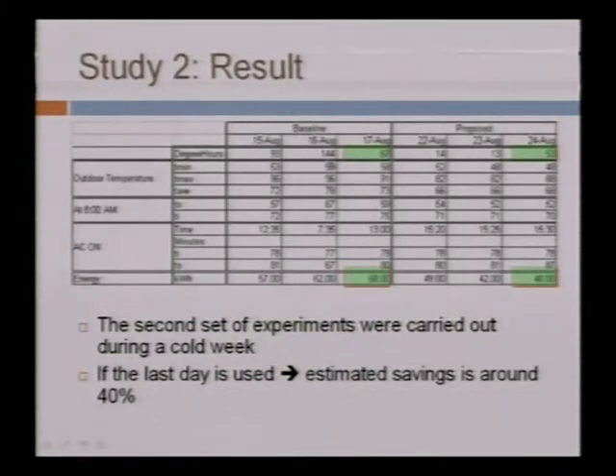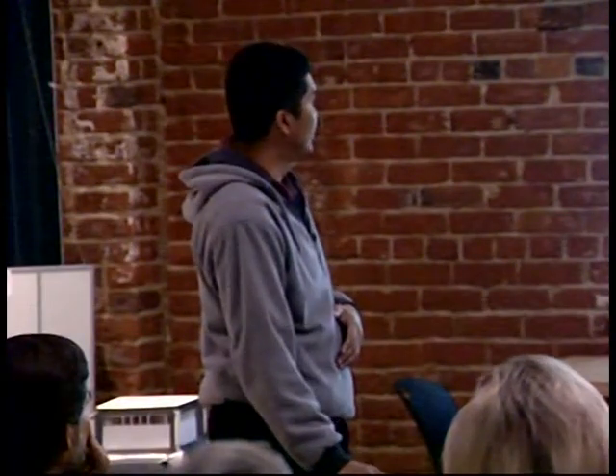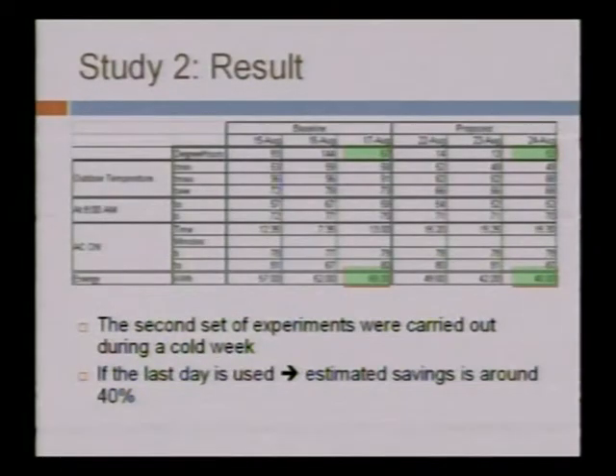But then again, we have the degree hours, which unfortunately, the proposed scenarios were carried out on a very cool week. Very cool week. So, if we want to compare, comparing this and this is not fair, because the cooling load is so much different. So if you compare the similar degree hours, which is on the third day, we can see that there is a 40% savings on the total energy, not only for the air conditioning, but for the total energy consumption.